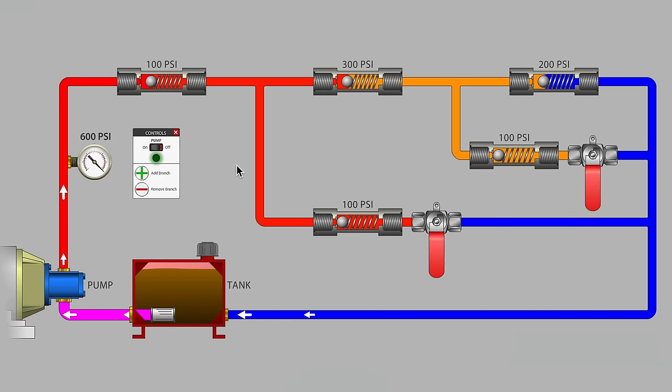So, in your hydraulic system, if you were expecting 200 PSI when you turned the system on, and yet you got 600 PSI system resistance, that would be a pretty easy way to understand that flow is not occurring in this branch. If you were expecting it to occur in this branch, then you've got some information that you can use. Something is now indicating that there must be blockage or very high resistance to flow in this particular parallel branch.